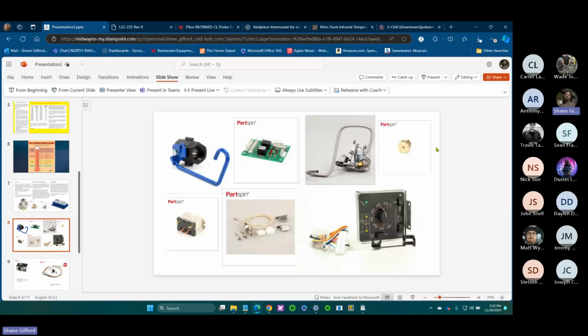So when we were getting those Jade fryers in and they weren't working, they wouldn't last. What we didn't know was that the spuds were incorrect. I believe on some of the fryers that they sent up to us to install, they were equipped with liquid propane orifices instead of natural gas. And they just simply will not work. That would be like trying to run an R448 TXV when you're trying to run, I don't know, 134A or something like that. It is just not going to work, right?